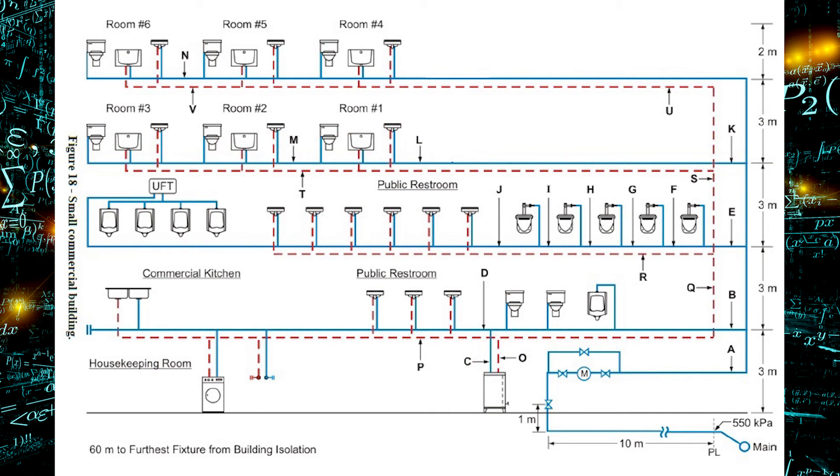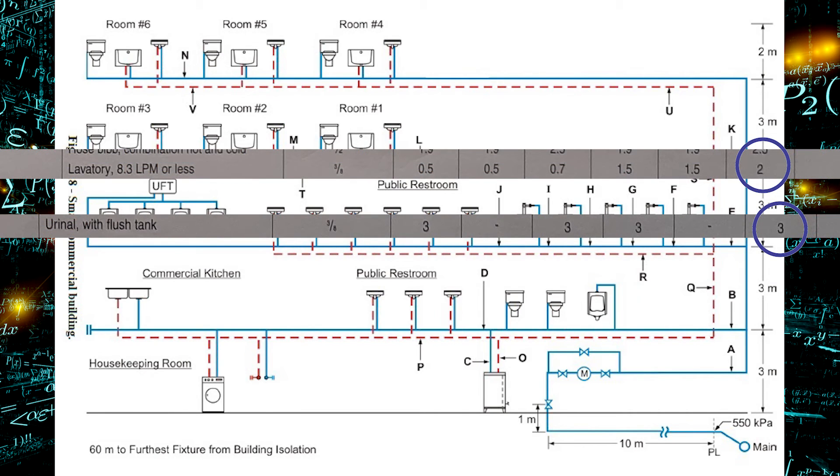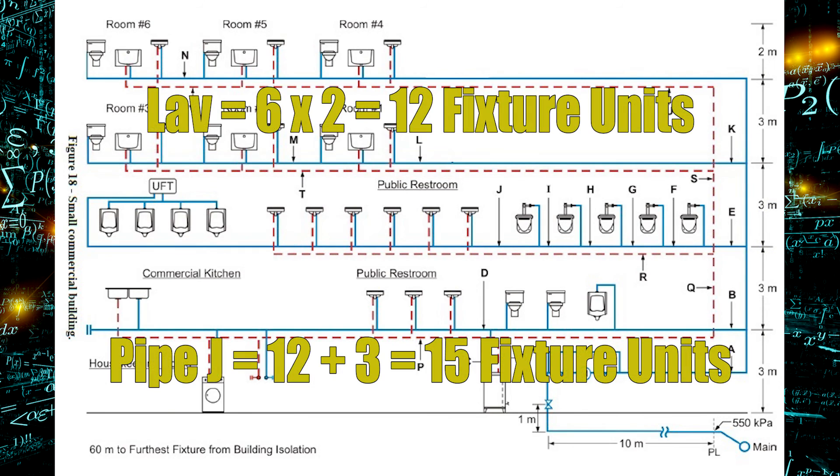On the second floor, let's look at pipe J. That's a cold water line, and that's providing water to six lavs and one urinal flush tank. That's what that is on the left-hand side. The urinal flush tank is three fixture units, and the lavs are two fixture units each. So six times two is 12 fixture units, plus the three. Pipe J needs to supply 15 fixture units.